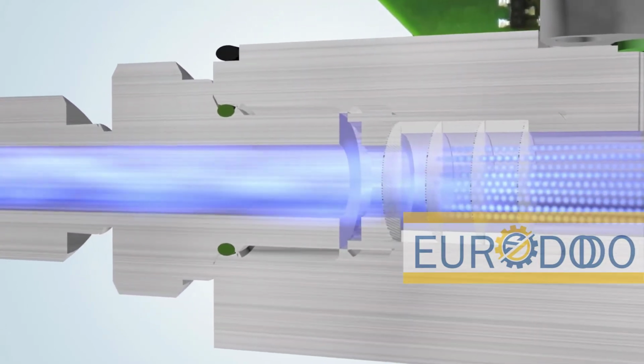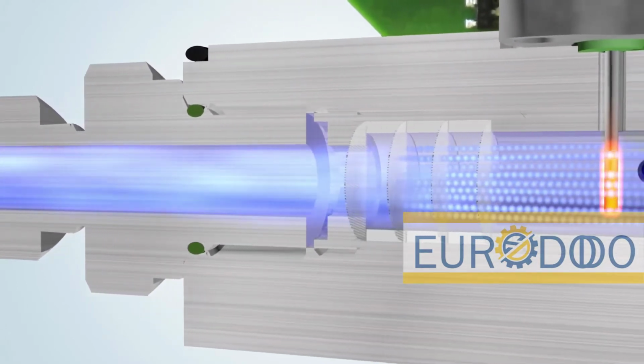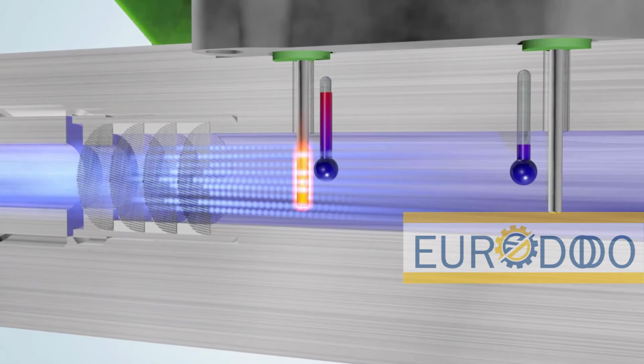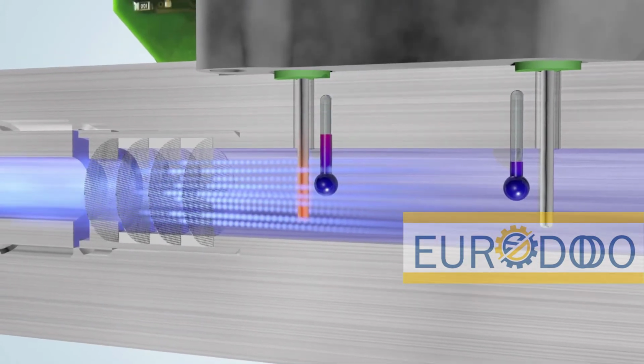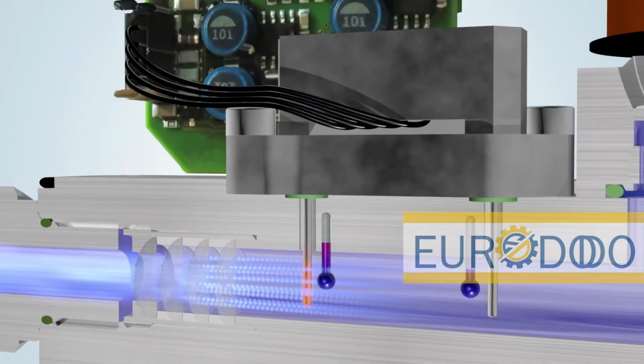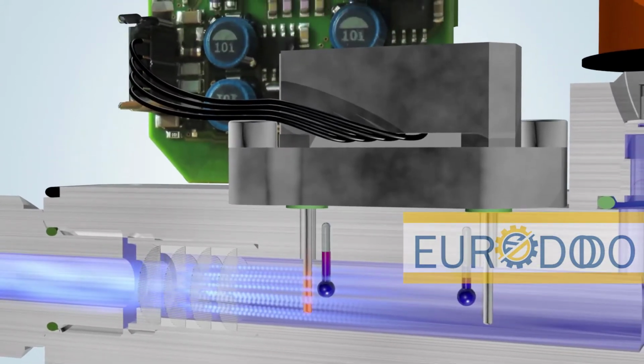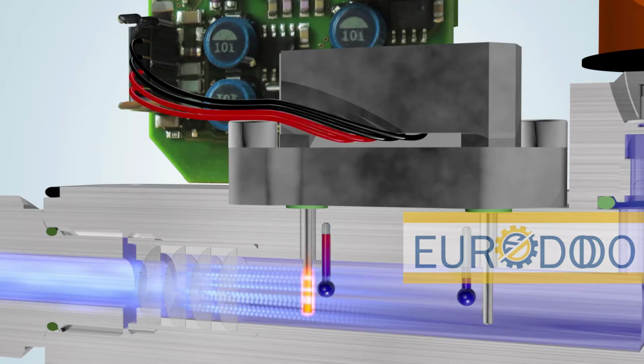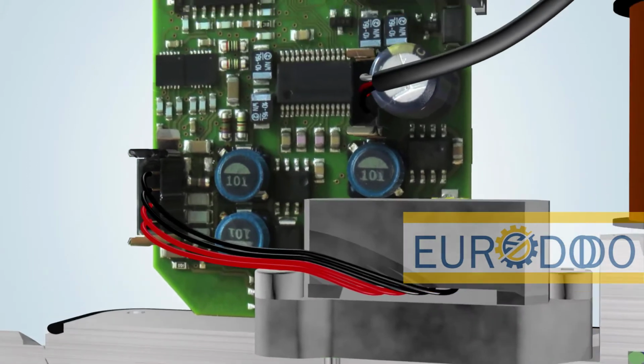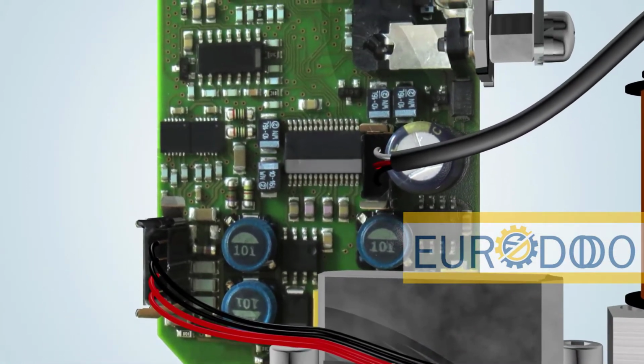The flowing gas cools the heater probe, and the comparator registers that the temperature difference between the two probes decreased. More energy is applied to the heater probe to maintain the desired constant temperature difference. This increase in heater energy is directly proportional to the mass flow as originally set out in King's law. The higher the flow, the more heater energy is needed.